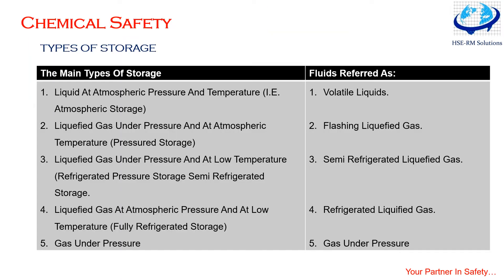We have defined five main types of storage with reference to the fluid. First: liquid at atmospheric pressure — atmospheric storage; these fluids are referred to as volatile liquids. Second: liquefied gases under pressure at atmospheric temperature — pressurized storage; these fluids are called flashing liquid gases. Third: liquefied gases under pressure and low temperature — refrigerated pressure storage; such fluids are called semi-refrigerated liquefied gas. Fourth: liquefied gas at atmospheric pressure and low temperature — fully refrigerated storage; fluids referred to as refrigerated liquefied gases.